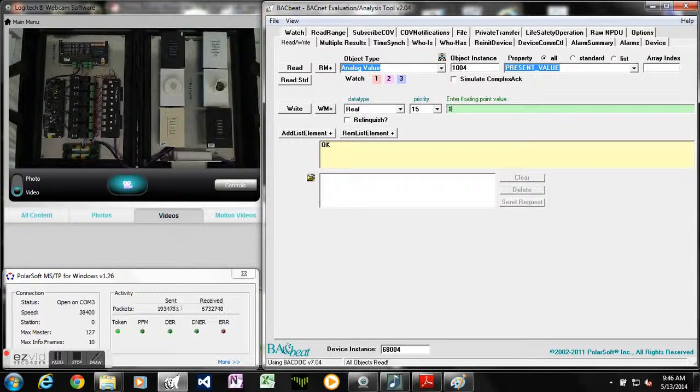So we can put our value in here and write our 1. So it works just like I pushed button number 1. If I push it again, it cycles on and off. Same for button number 3. And turn on button number 4. And button number 5. And then my button number 6 is currently programmed as like an all off. So if I hit number 6, it'll turn all those off. So it's just remote button presses is essentially what the input emulation is for object 1004.